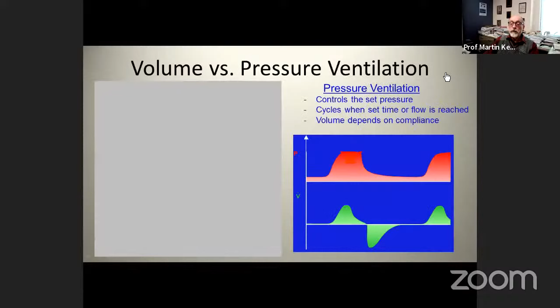The flow pattern of volume guarantee is the same as for pressure controlled ventilation. So here's your pressure, the circuit is pressurized, flow enters and results in a certain tidal volume. So it is still pressure controlled ventilation, but this peak pressure is being adjusted in real time. Volume controlled ventilation is a different modality altogether. There's continuous flow of gas into the patient circuit, and pressure rises passively, reaching peak just before exhalation. So volume controlled ventilation is different. Volume targeted ventilation, volume guarantee, is pressure controlled ventilation with volume targeting. Okay, so important distinction.